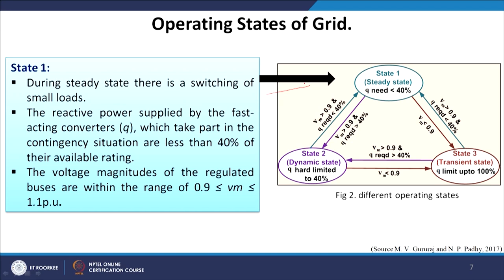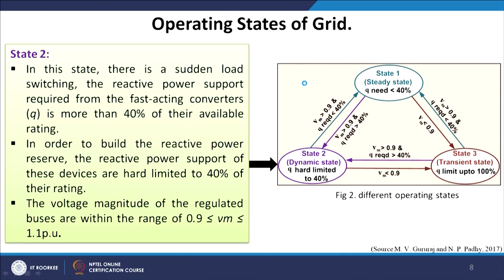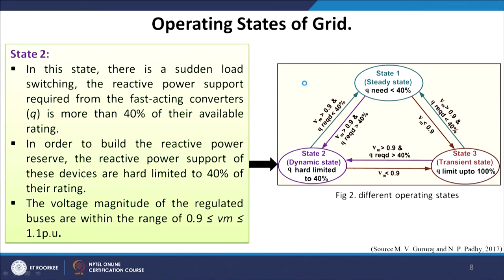During steady state, the voltage magnitude of the regulated buses is within 0.9 to 1.1 per unit. Moving to the dynamic state, any sudden load changes fall under this stage. The reactive power support required from the fast-acting converters is more than 40 percent of their available capacity. In order to build the reactive power reserve, the reactive power support of these devices is hard-limited to 40 percent.